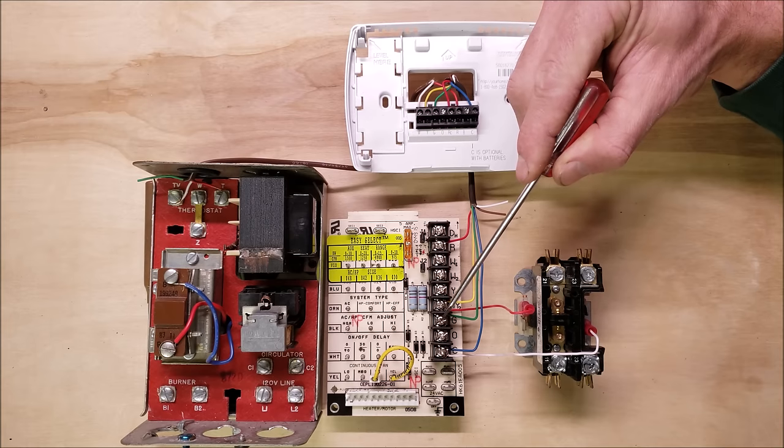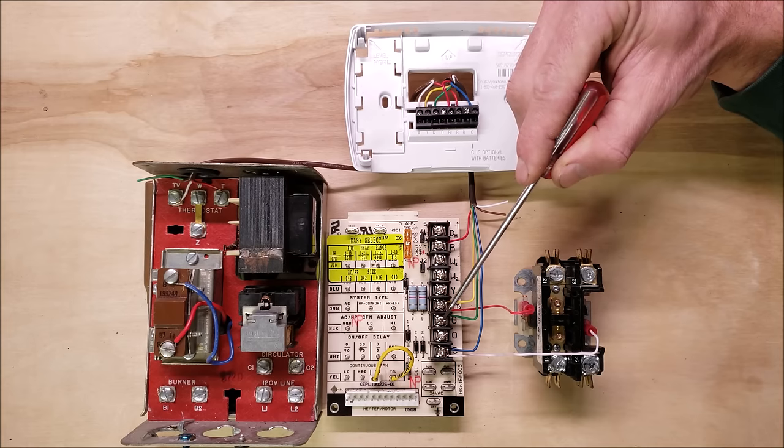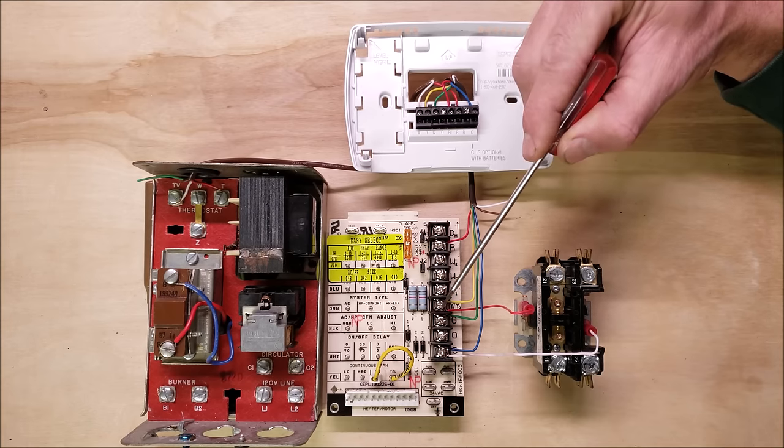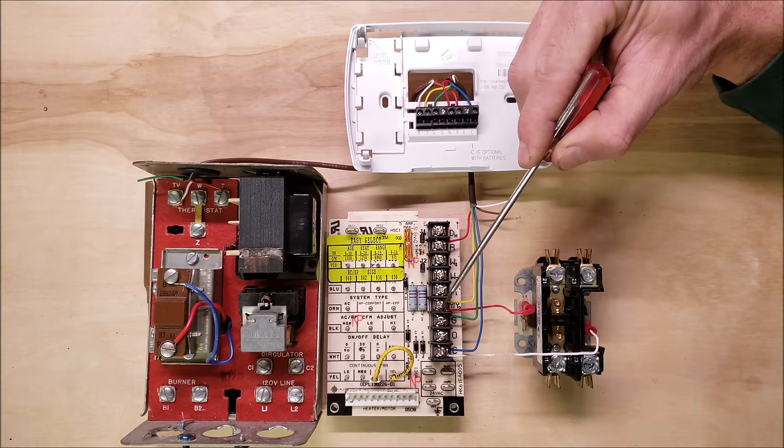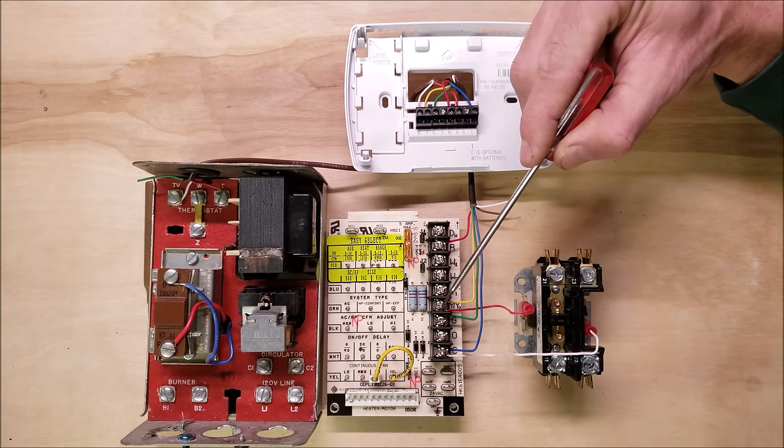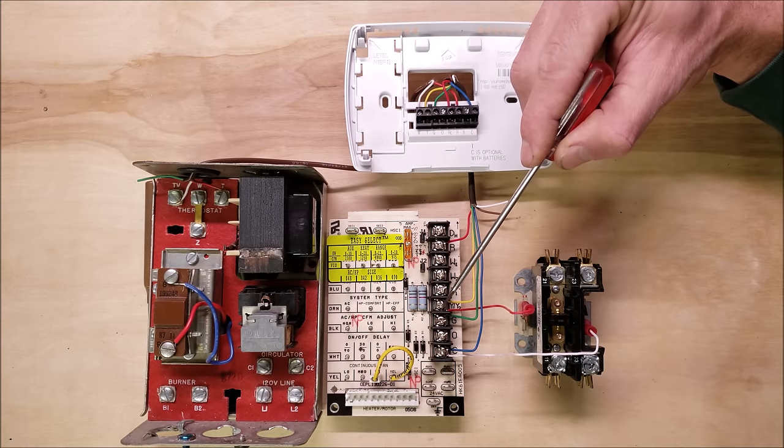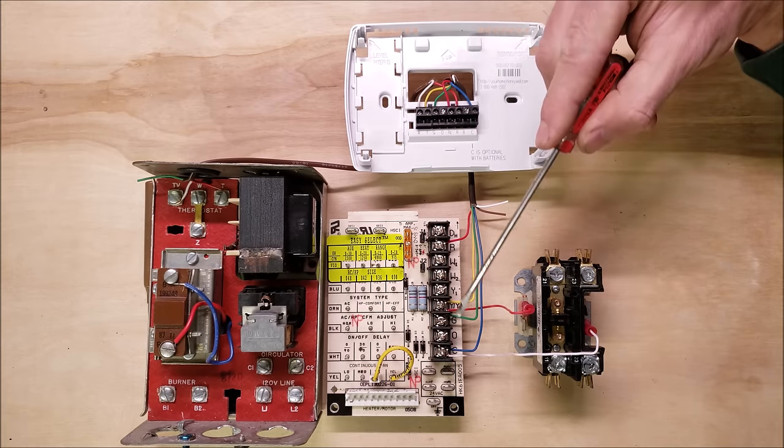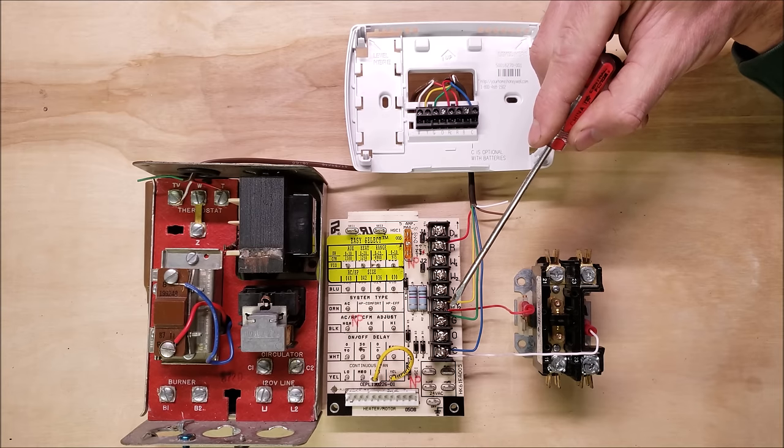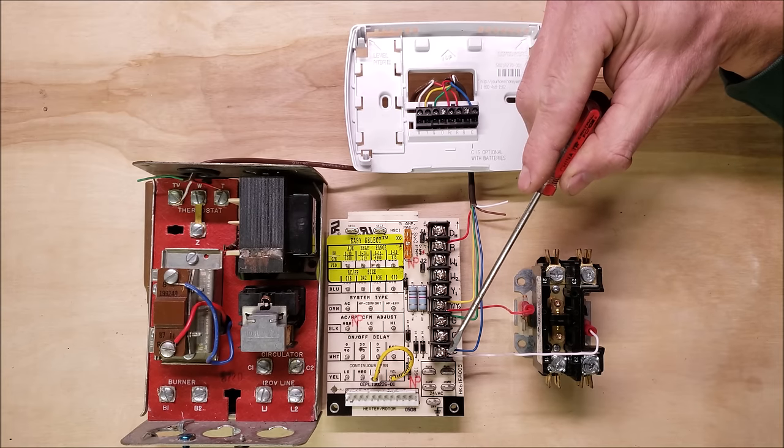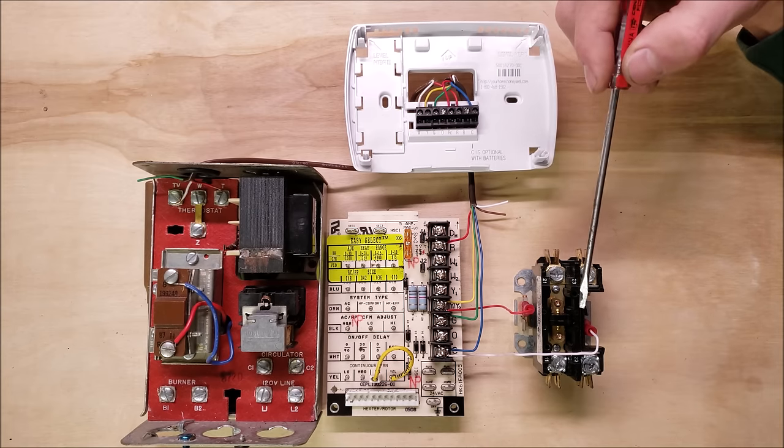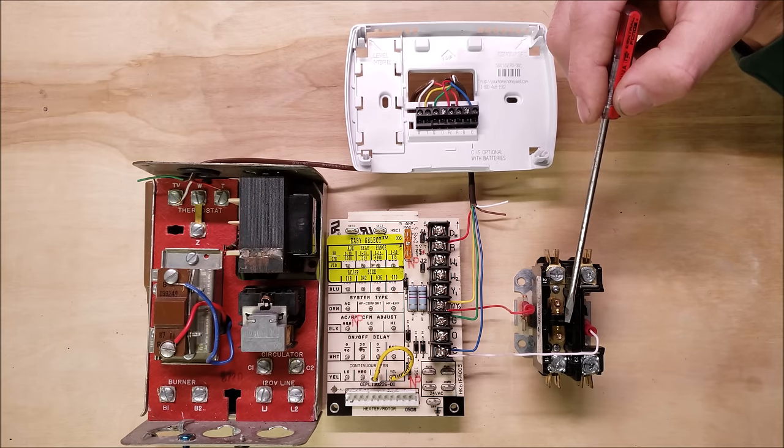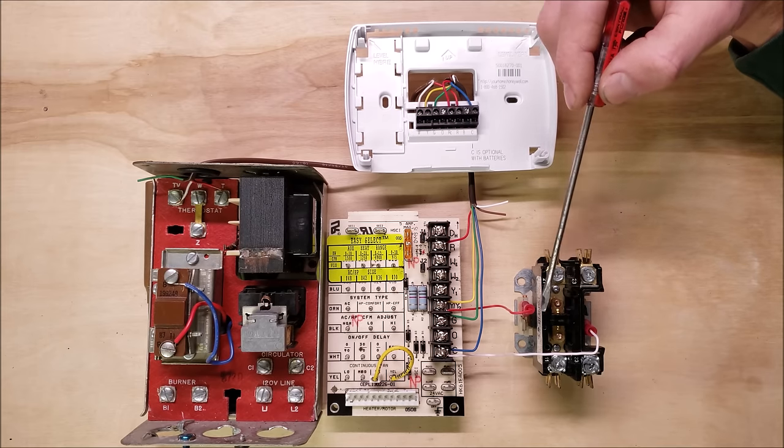G is going to tell your indoor air handler fan to turn on where Y is going to say we are on our cooling air speed. You're going to also notice a second wire on Y and a second wire on C heading over to the contactor, turning the compressor on.